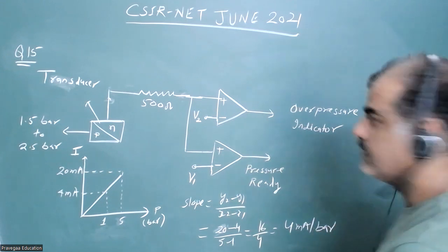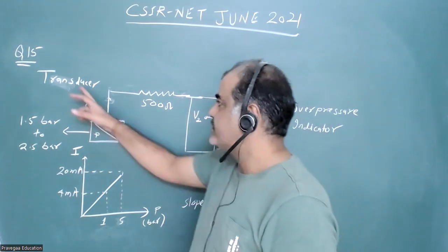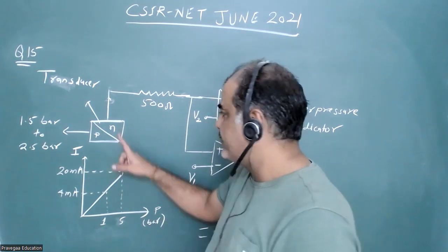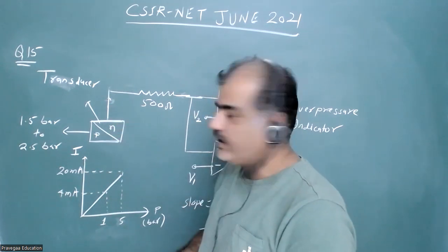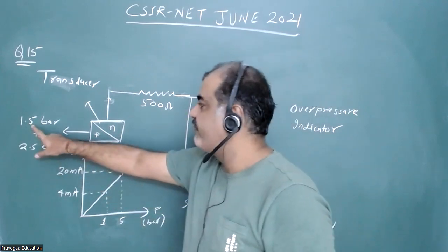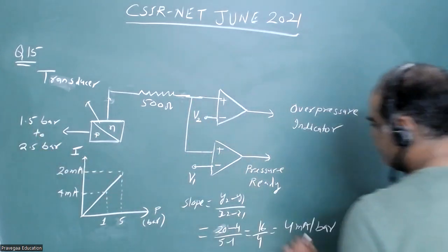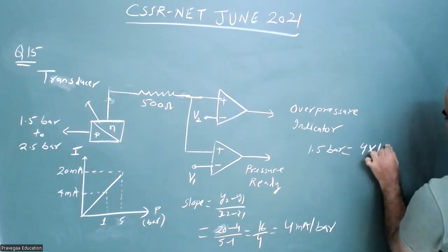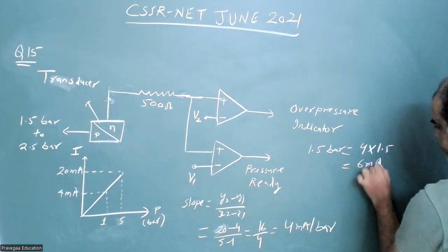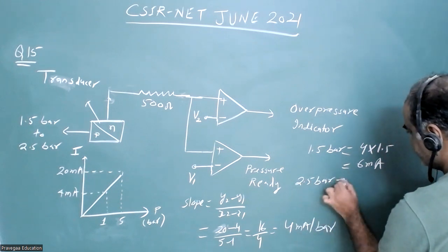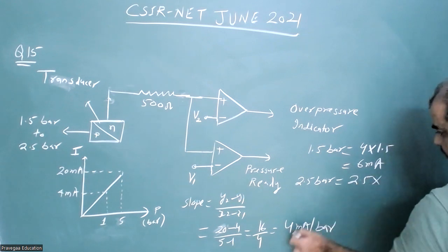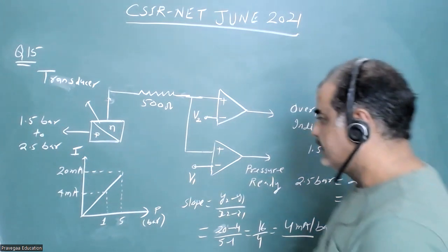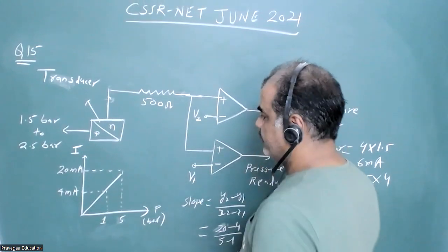The output of the transducer is 4 milliampere per bar, and this output is linear. So whatever pressure is there, we get a linear current output. For 1.5 bar, the current is 4 × 1.5 = 6 milliampere. Similarly, for 2.5 bar, the current is 4 × 2.5 = 10 milliampere.